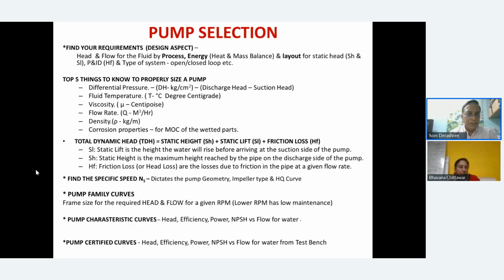So you have to find this out. Then find the specific speed. Now that is a very, very important parameter, often not taken care of during the design stage, but it is at the design stage that you can make use of this. Now, what is this specific speed? It dictates the pump geometry, impeller type, and the HQ curve, that is the head versus flow curve. Now, very, very important parameter. We'll delve a little more into this in the subsequent slides.